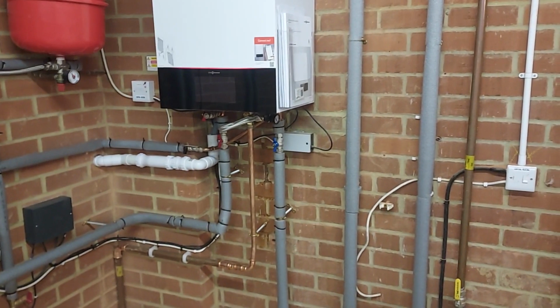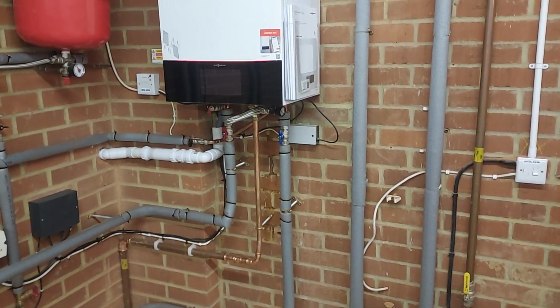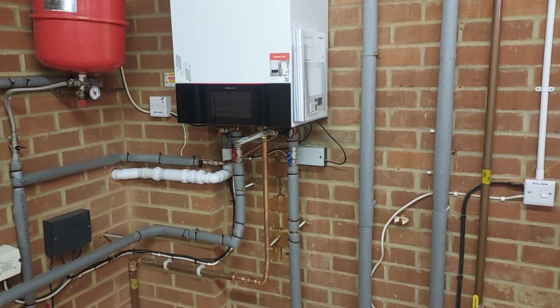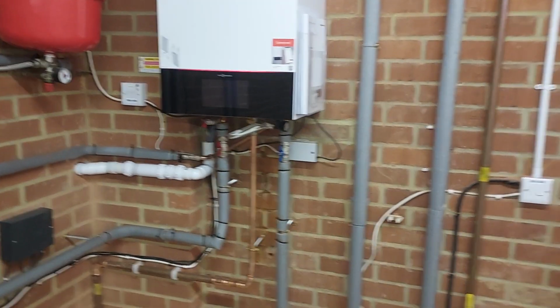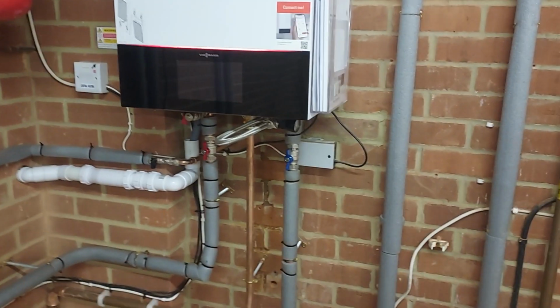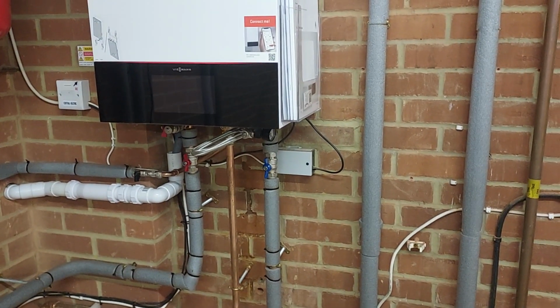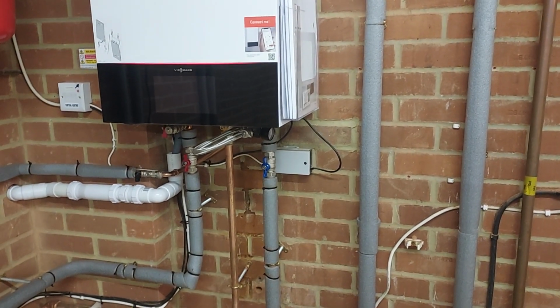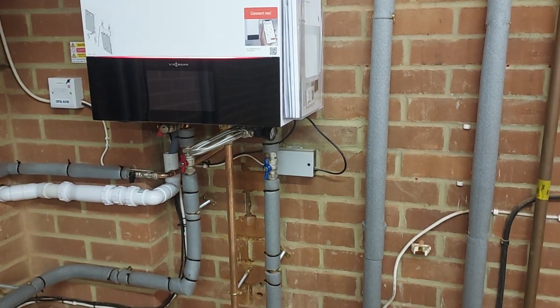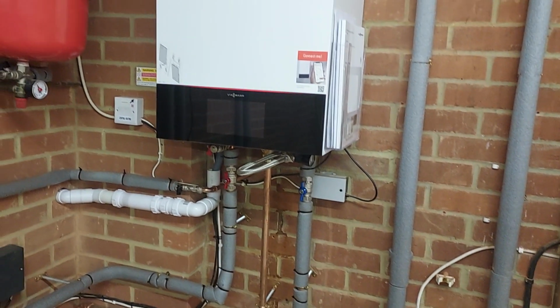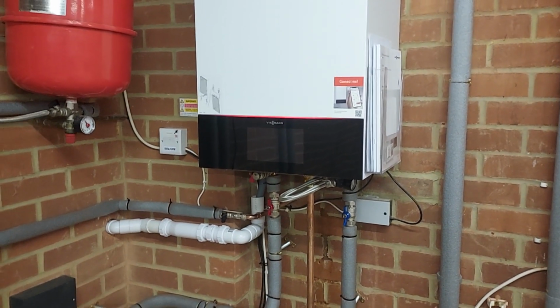I've got a cylinder demand relay there because we can't use 2 sensors on the Viessmann. It's the only limitation of the Viessmann compared to the Vaillant as far as I'm concerned. But anyway, that's our compromise there - the boiler either thinks the order is 75 or about 20 or something, so one's on and one's off.